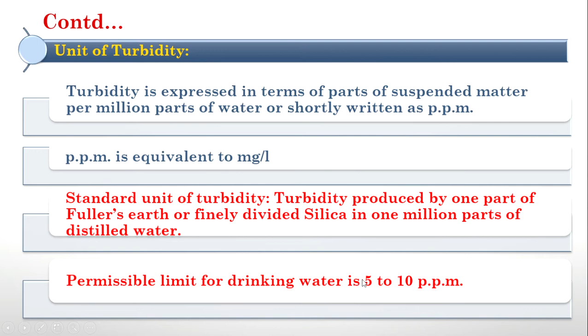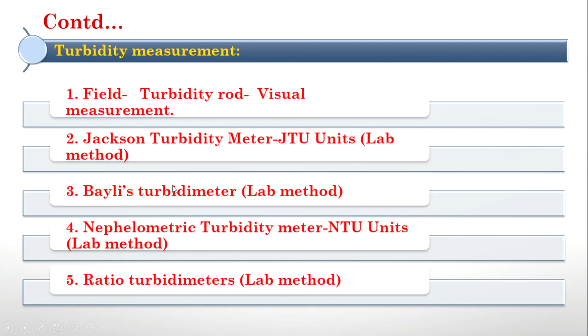There are many measurement devices for measuring turbidity. In the field, we will measure the turbidity by means of a turbidity rod. In a lab, we have many other instruments: the Jackson turbidity meter, which measures turbidity in JTU units, Jackson turbidity units; Bailey's turbidity meter, which measures turbidity in BTU units, Bailey's turbidity unit; and nephelometric turbidity meters and ratio turbidity meters. We will see each of them.